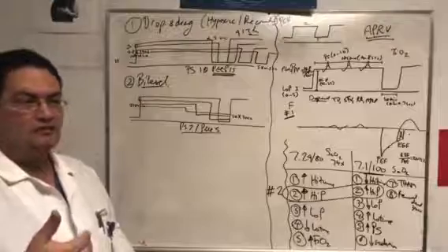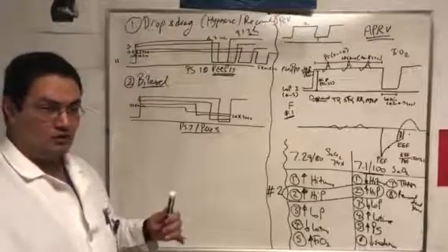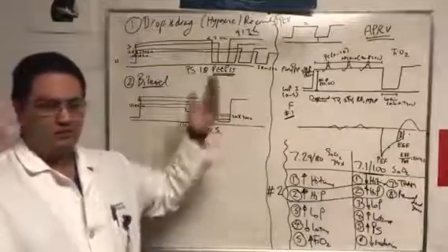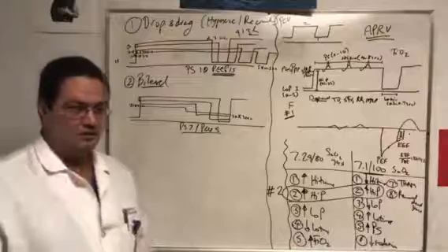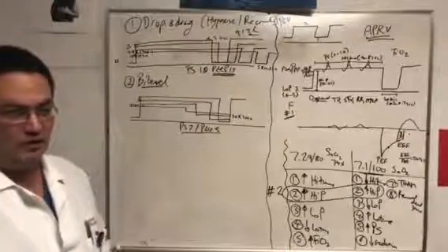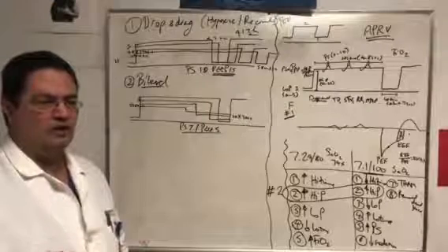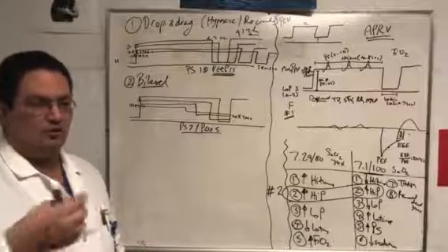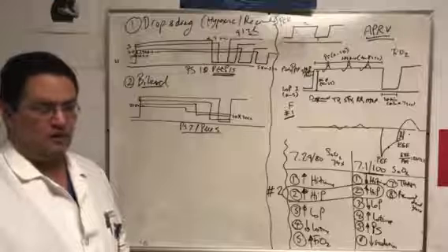We don't measure this ratio when we do bilevel, because nobody's going to get hurt with it. It allows the patient to exhale all the way. So when we go 1 second or more, we are in bilevel territory.